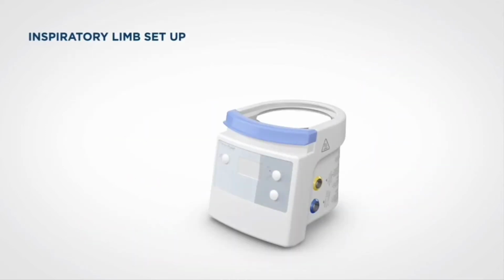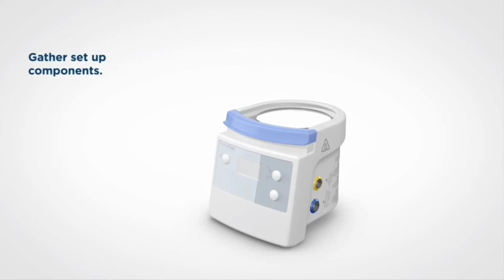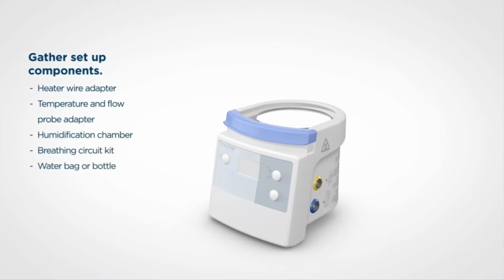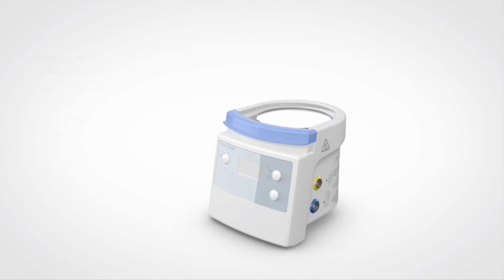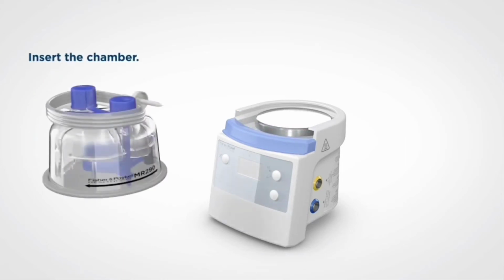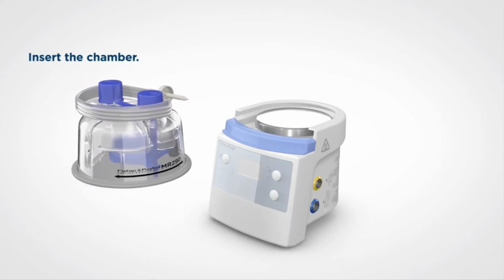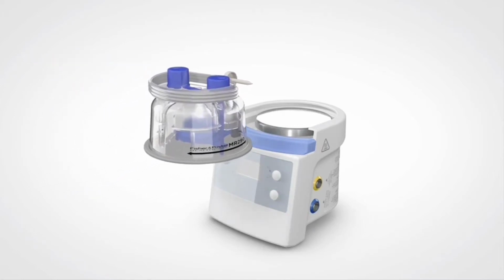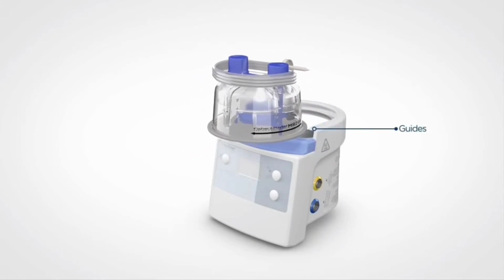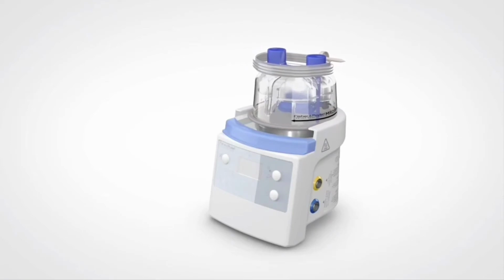Let's now look at how to set up the humidification chamber and breathing circuit on the MR850 humidifier. Start with the humidifier turned off. Gather the components required for setup, including the heater wire adapter, temperature and flow probe adapter, humidification chamber and breathing circuit kit, and water bag or bottle. Open the breathing circuit bag and take out the humidification chamber. Push down the finger guard and slide the humidification chamber onto the humidifier heater plate, making sure the aluminium base of the chamber slides under the guides on either side of the heater plate. The chamber should slide to the back of the heater plate until the finger guard springs back into place.